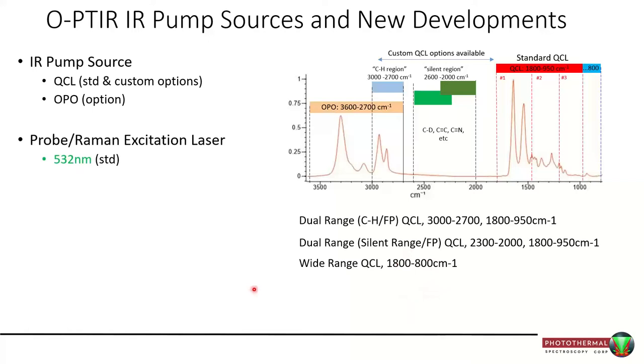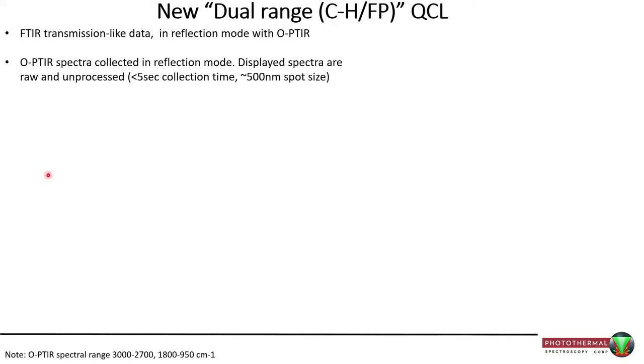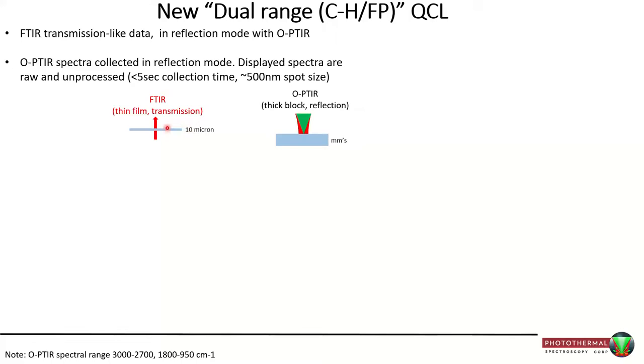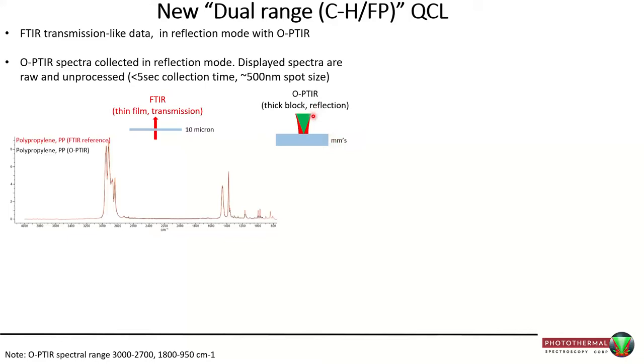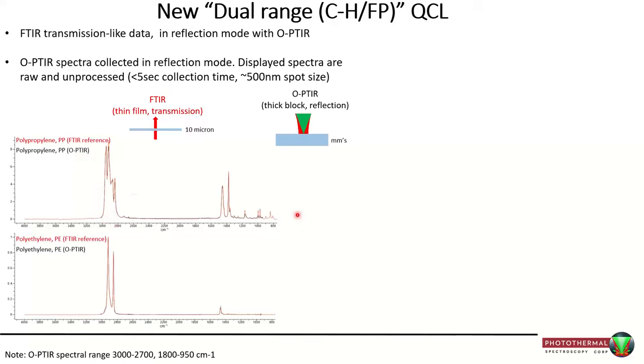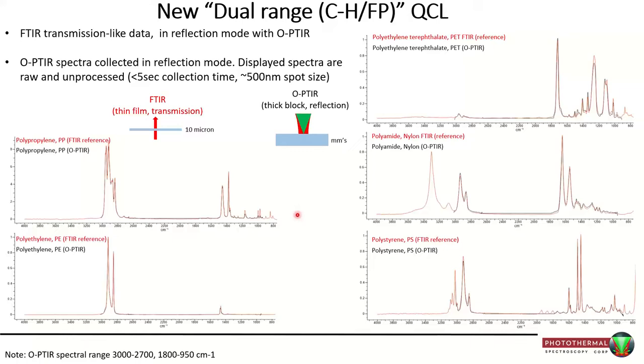The probe beam also doubles as the Raman excitation laser — you can opt for 532 nm or 785 nm. It's important to appreciate that OPTIR spectra are very much compatible and comparable to decades of FTIR history and libraries. Comparing transmission FTIR library spectra of thin films against OPTIR spectra of thick blocks measured in reflection mode, examples including polypropylene, polyethylene, PET, nylon, and polystyrene show a spot-on match. These spectra are raw — no treatment or transformation — exactly what you see on the screen.